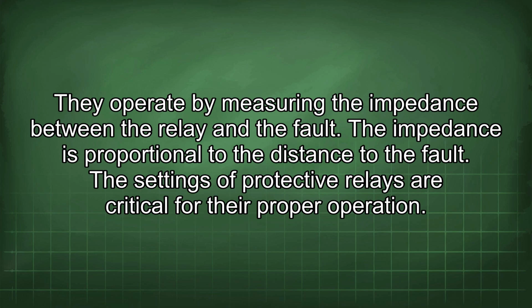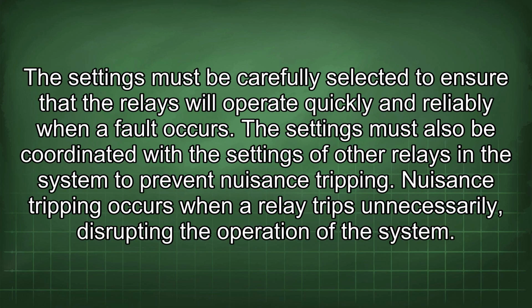The settings of protective relays are critical for their proper operation. The settings must be carefully selected to ensure that the relays will operate quickly and reliably when a fault occurs. The settings must also be coordinated with the settings of other relays in the system to prevent nuisance tripping. Nuisance tripping occurs when a relay trips unnecessarily, disrupting the operation of the system.